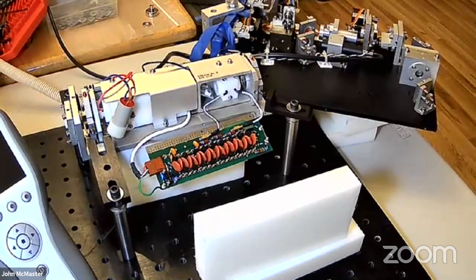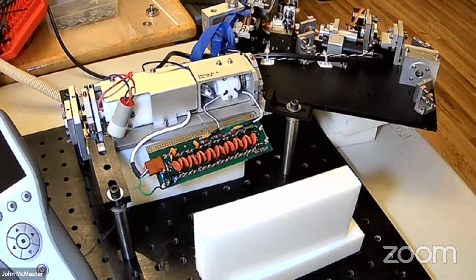All right, so now that we have a rough idea of what the laser alignment is, we put in this polarization. The next thing to do is to put, remember I said we took all the stuff out? We're going to put this quarter wave plate back in, but initially not at the final configuration, but something that's going to rotate the polarization back such that we actually make it through that Brewster plate. There are very fine adjustments you can make by rotating it. We're going to put this in, and then rotate it until the laser starts firing again. That means it's passing enough light polarized in the way that we get light out of the laser. So basically they cancel each other out, so to speak.